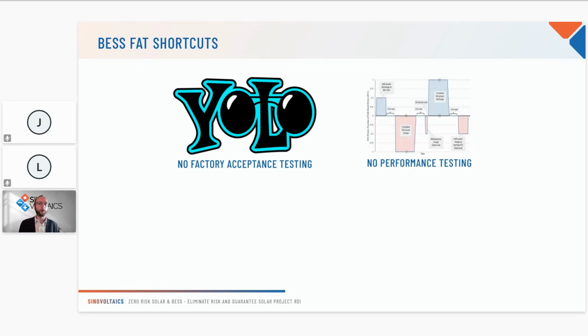Second, you have no performance testing, meaning the manufacturer will only do visual inspection, making sure you have your nice logo on the container, but they won't test anything else. Again, they have done battery module testing, it was working well, so there is no reason it will not work at the container level. And spoiler alert, they are extremely wrong.